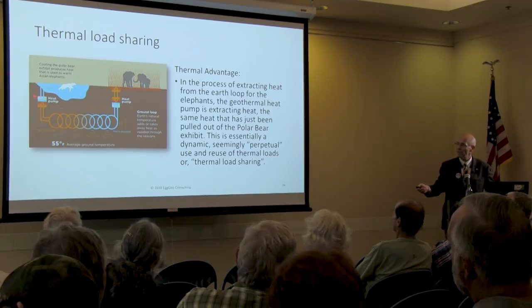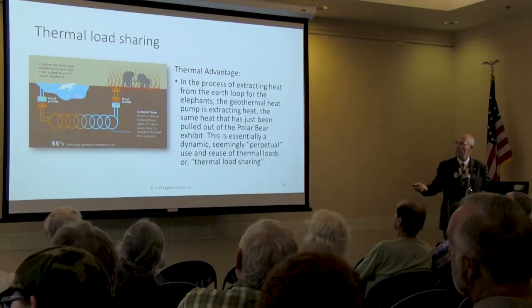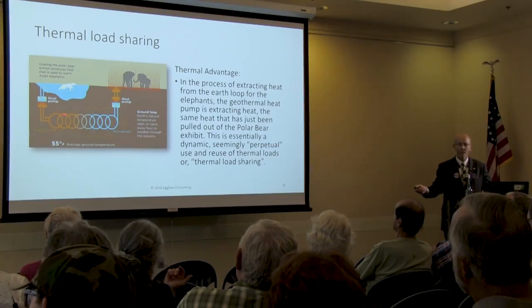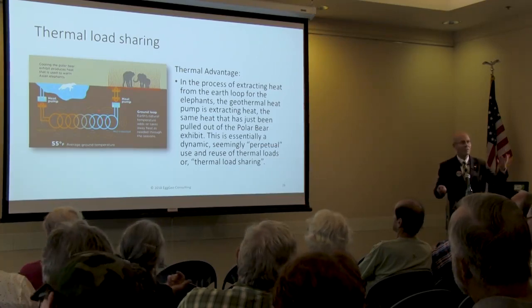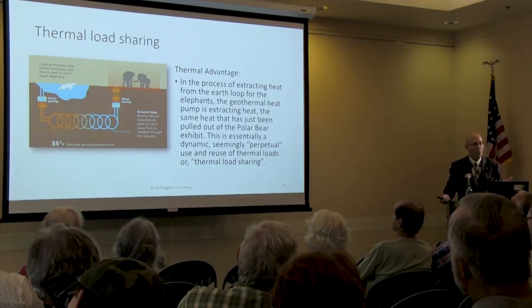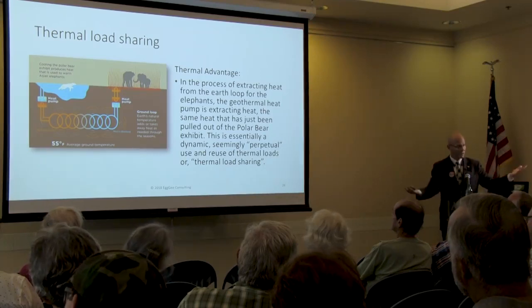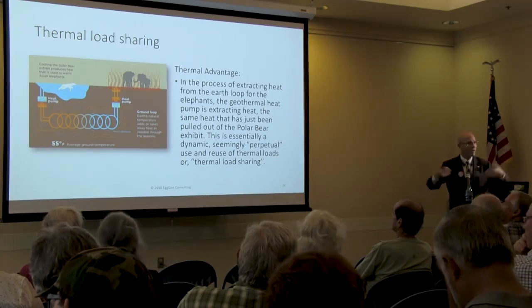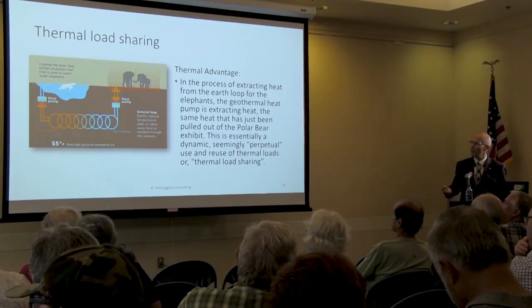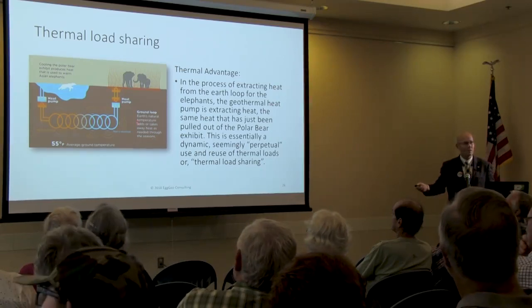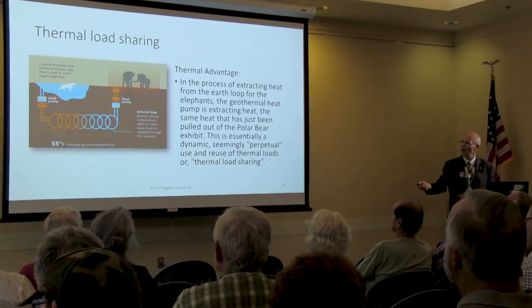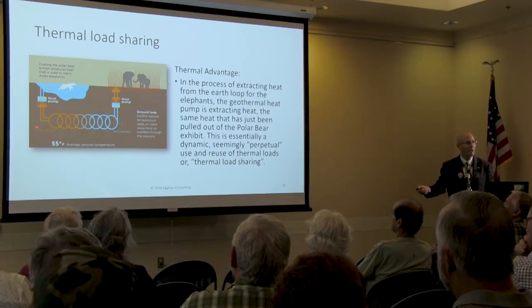Now, these heat pumps can either heat or cool. So they need this polar bear exhibit at 40 degrees. So what happens on a normal day like today, that water is absorbing BTUs. We talked about the sun just constantly heating up, especially during the summertime. So this heat pump is constantly pumping BTUs out of the polar bear exhibit and into the ground loop.